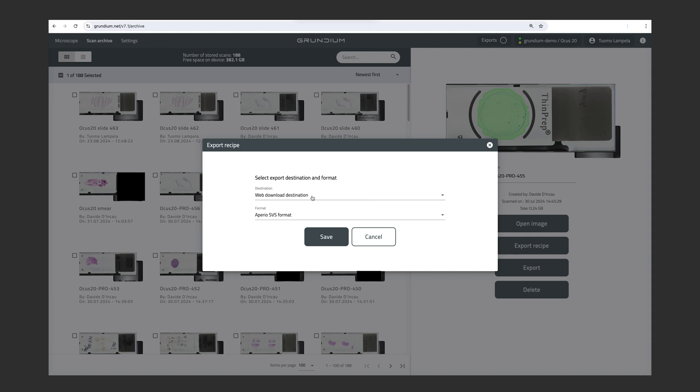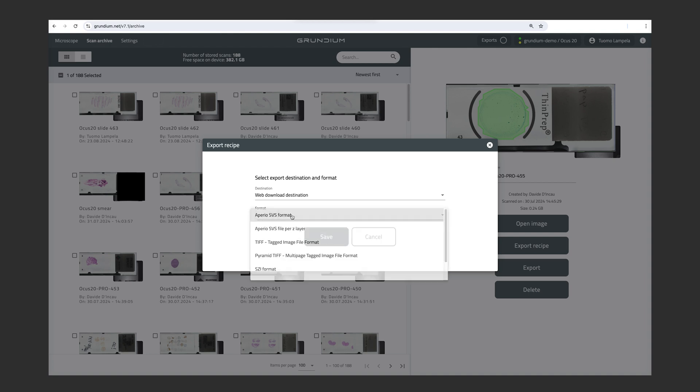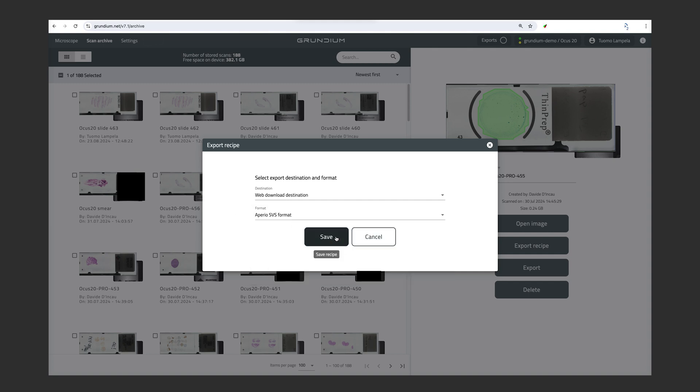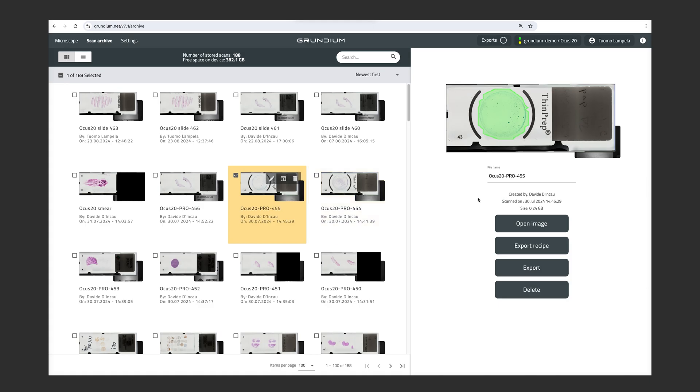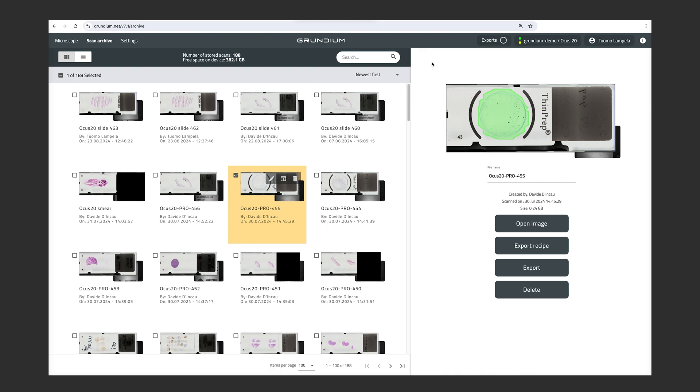And here we can choose where we want to export our images. And we have the option of SMB, which is a network drive. We have USB storage. And we have the web download destination, which actually means the browser download folder on the computer. So in this case, I'm going to choose the download folder of my computer. And then we have different formats also. And SVS and TIFF being the most common ones are available. And after saving the settings, I just click Export. And then you can see here up in the exports that it's exporting the image to my Downloads folder. And from all the export locations, you can import the image into your IMS, LIS, or any other software you need it.